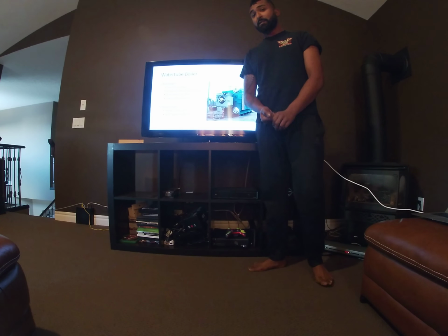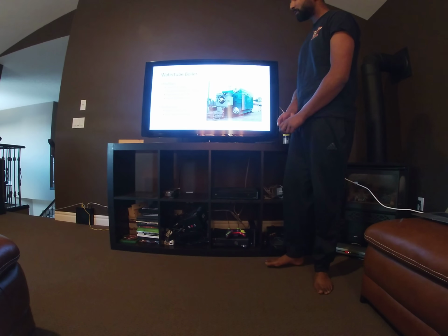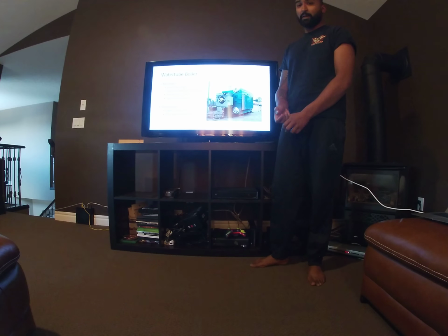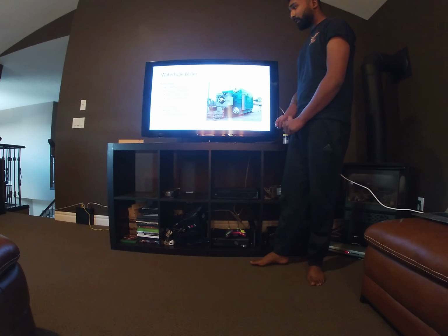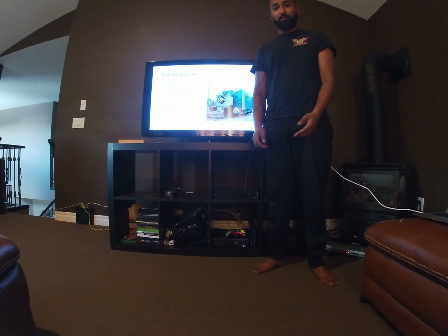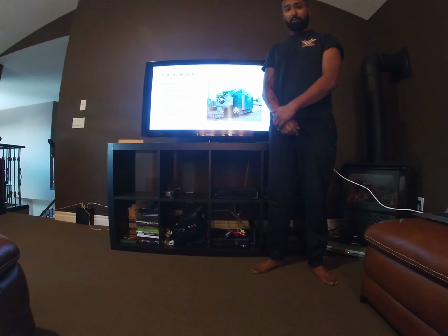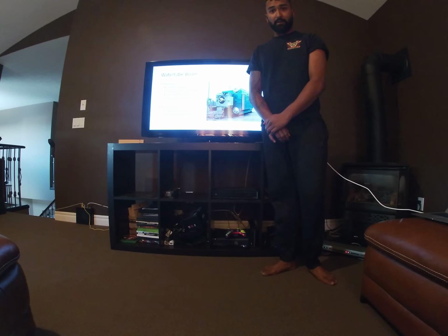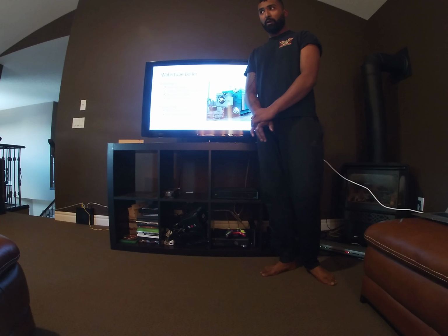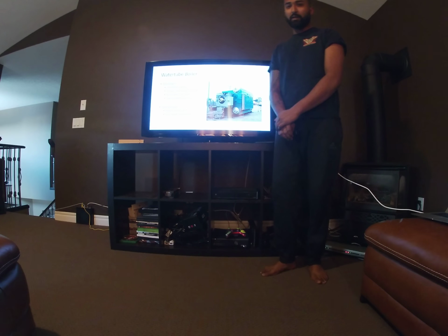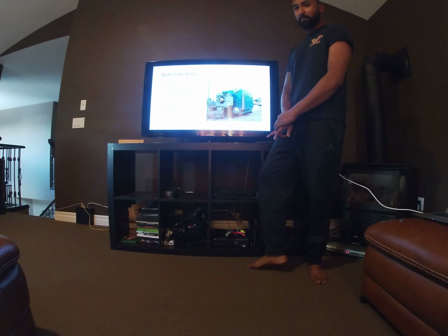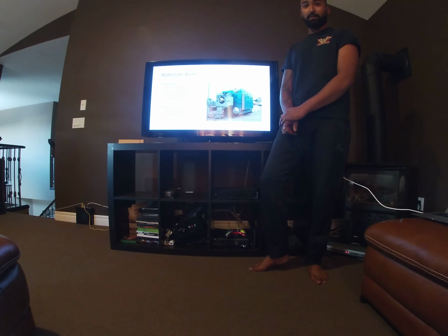Water tube boilers are next. We're just going to talk about their advantages. They have a very small floor space, same thing as a fire tube boiler. They require no special foundation, so they could be set wherever you need them. They have a short warm-up time because the amount of water in those boilers is not as much as a fire tube.